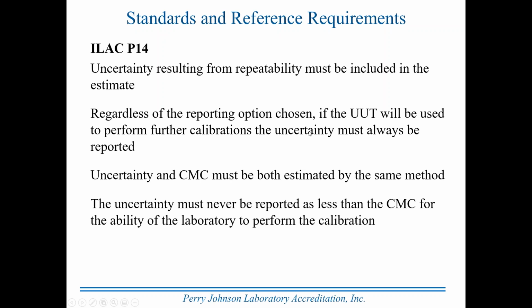That brings up this next one. The uncertainty must never be reported as less than the CMC for the ability of the laboratory to perform the calibration. If you're properly estimating the uncertainty and the CMC, then it cannot possibly be better than the CMC, because the CMC, again, would be the very best equipment under ideal conditions.